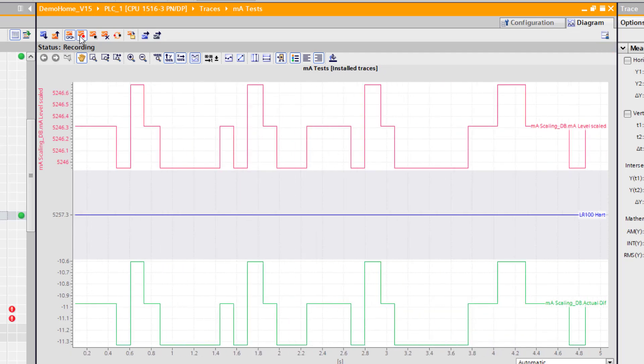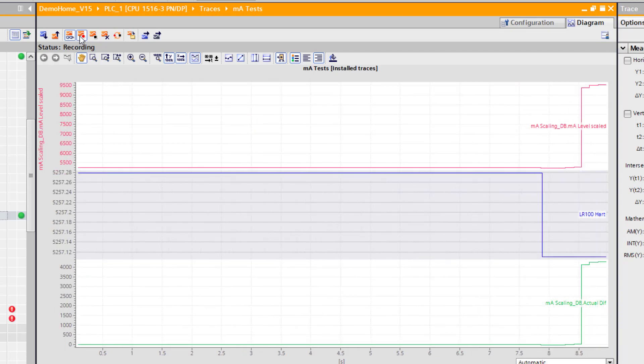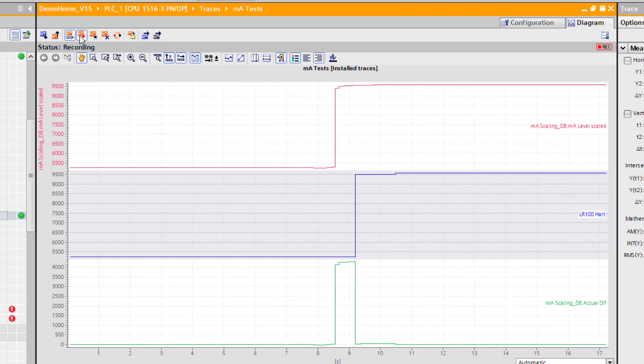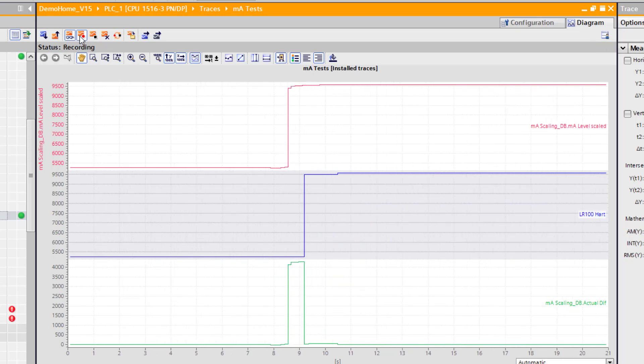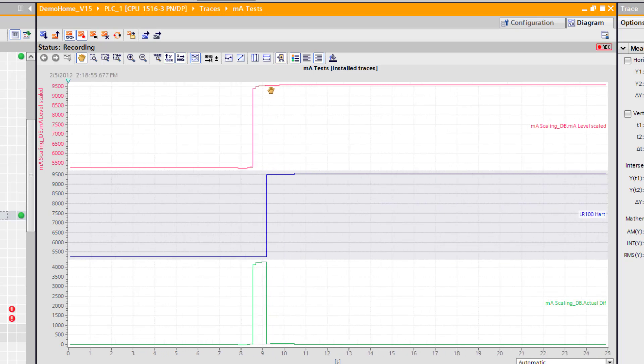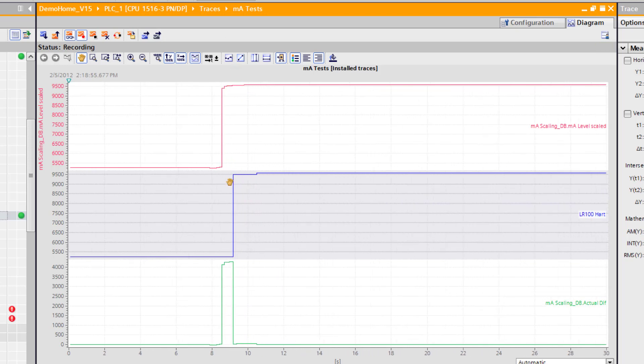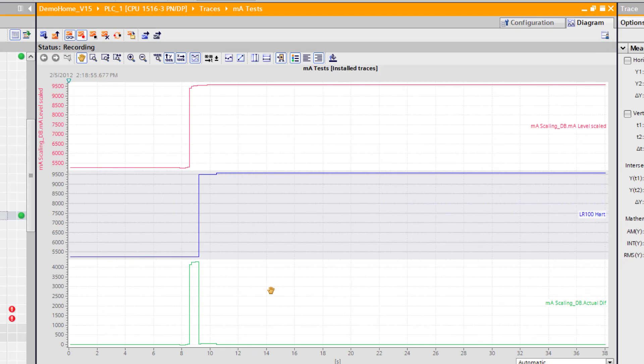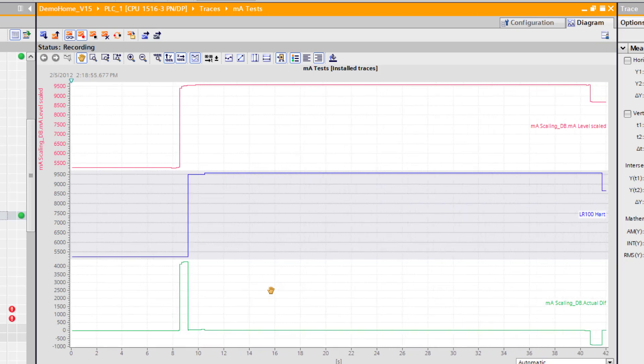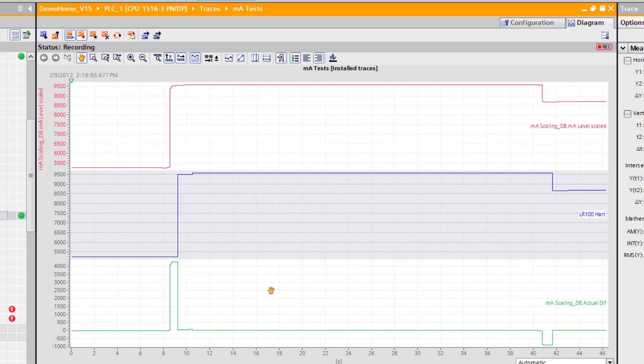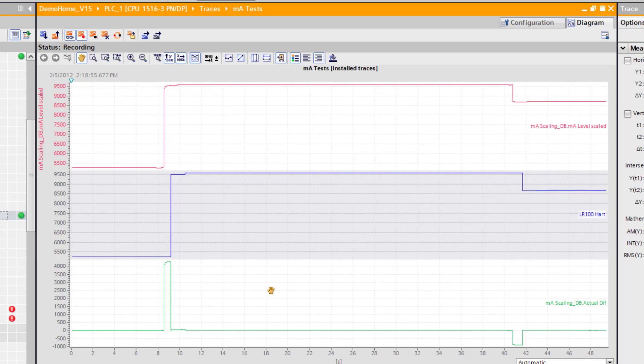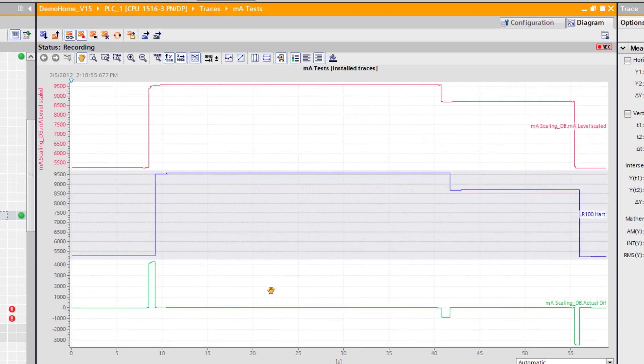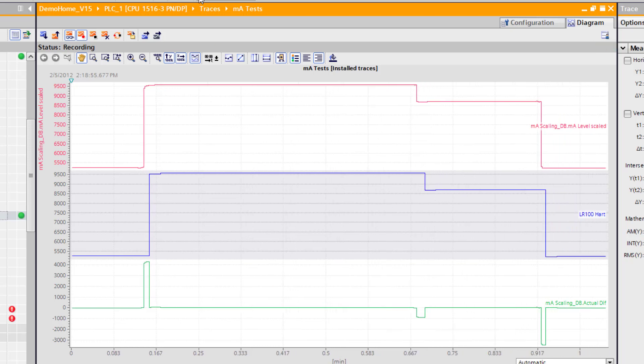It's auto-scaling so it looks a little bit messy to start off with, so I'll move it to the 4 meter value. The radar has got no filtering on it so it's reacting as quick as it can. We can see that the milliamps value is quicker, but by the time it's actually settled — to get to its best uncertainty value — they're pretty similar. We'll zoom in to see the actual time. Now I go to my one meter value — it's pretty consistent — and then back to our four meter value. There are the results.